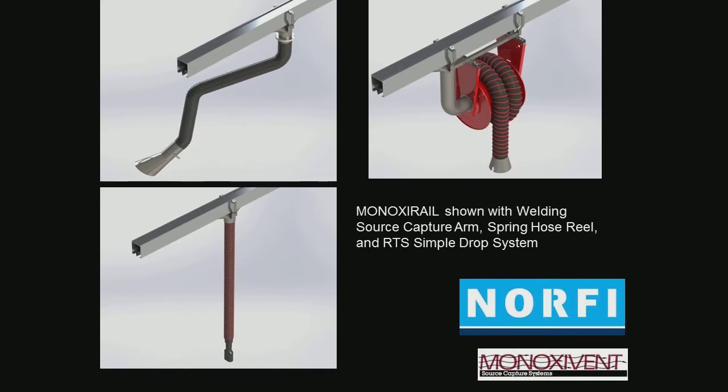So my next question to him would be, do you want to just designate 3 bays where you're going to put a running vehicle, and that's where we'll put the equipment? And he'll always say, no, I have 8 bays. I want to be able to use any of the 8 whenever I want to. So theoretically, I should put 8 drops in, 1 drop per bay. But perhaps I could save him some costs and put a drop in between bays. So I drop from 8 to 4, but the design flexibility is gone because he could never run an engine in bays 8 and 7 at the same time because there's only 1 drop in between the two.